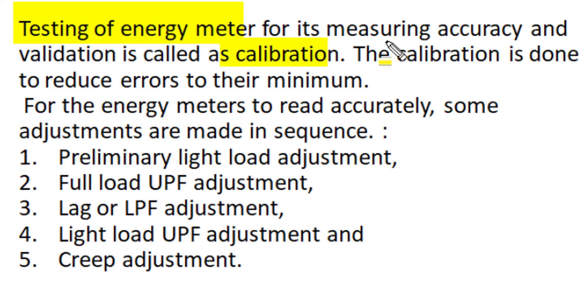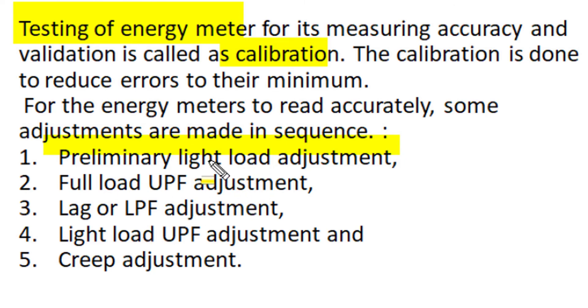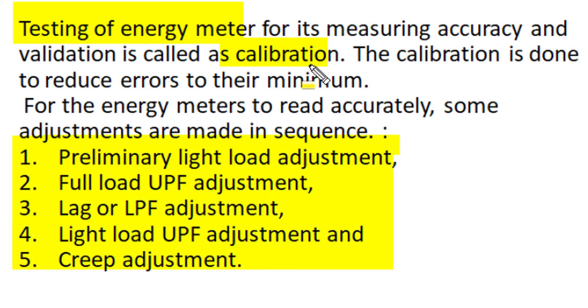Testing of an energy meter for measuring accuracy and validation of that accuracy is called calibration. Calibration is done to reduce errors to a minimum. For accurate measurement, adjustments are made in a specific sequence: first, preliminary light load adjustment; then full load at unity power factor; then full load at 0.5 lagging power factor; then light load at unity power factor; and finally, creep adjustment is tested.